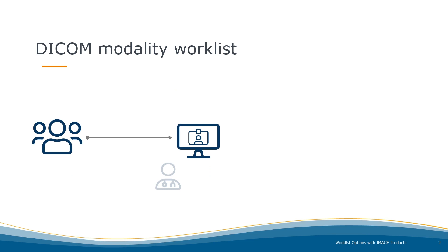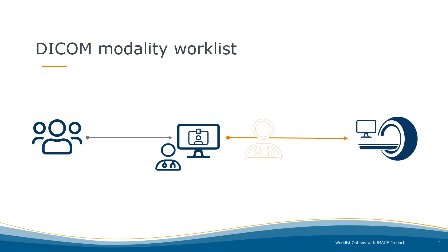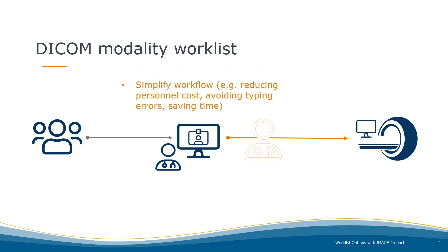With a DICOM modality worklist, many of these errors can be avoided. The patient data must still be entered manually into the information system, but it can be transferred directly into a digital worklist, which is then automatically transmitted to the device. This way, the patient and study data end up directly at the place of action, saving time and avoiding typing errors.